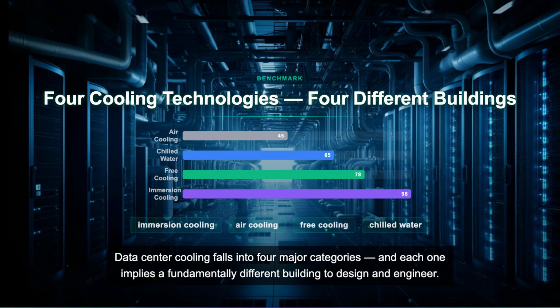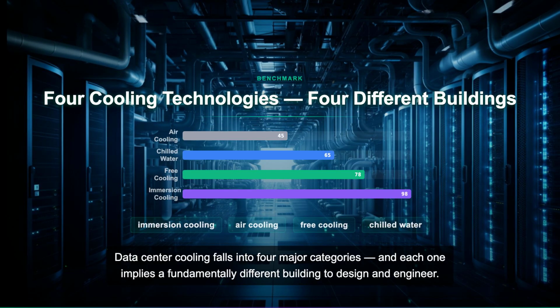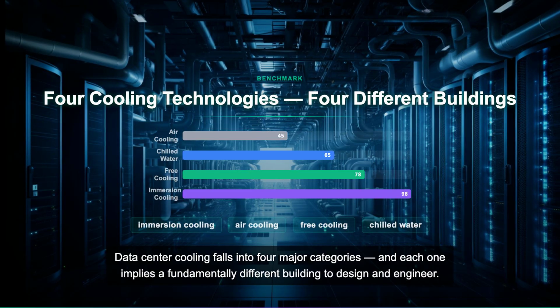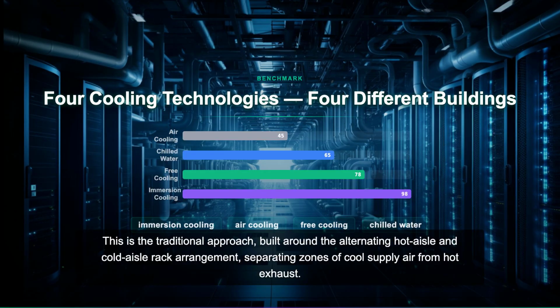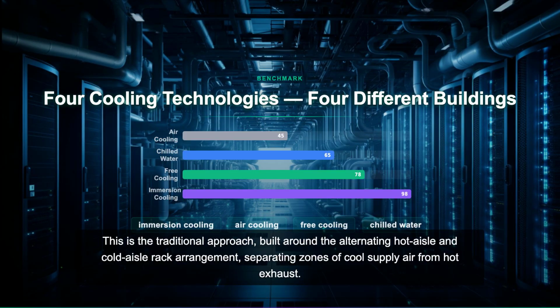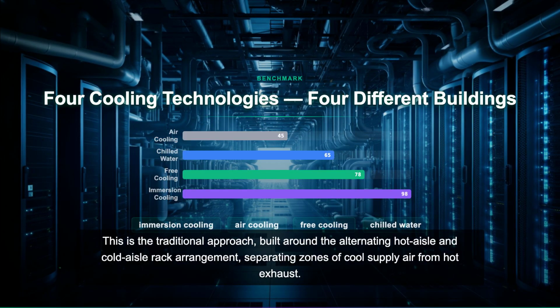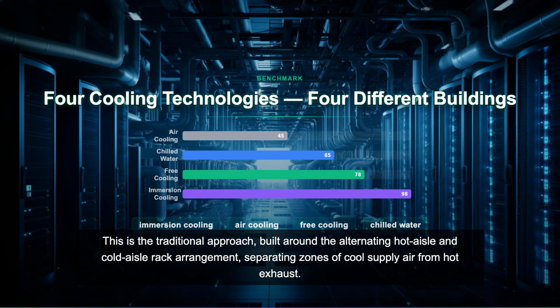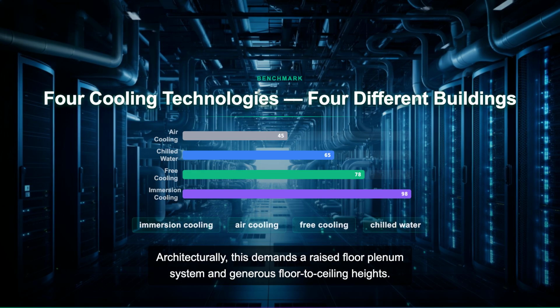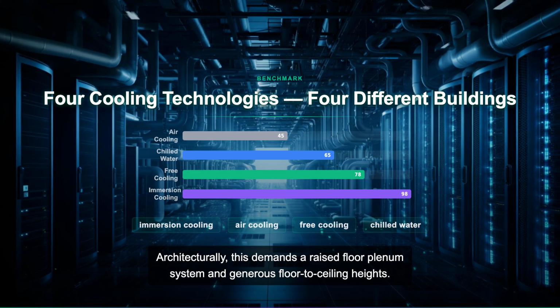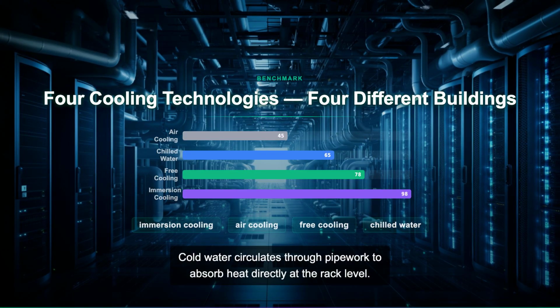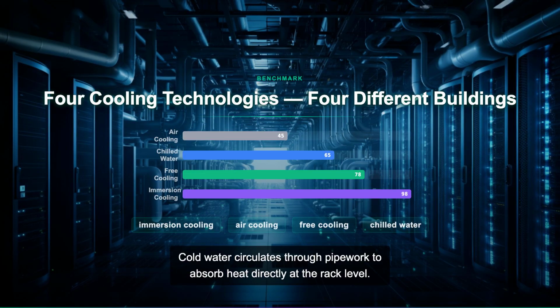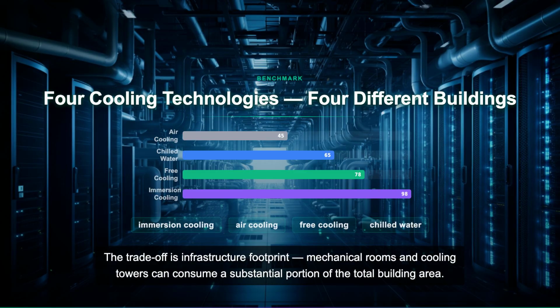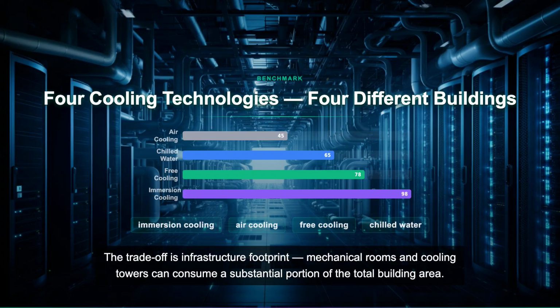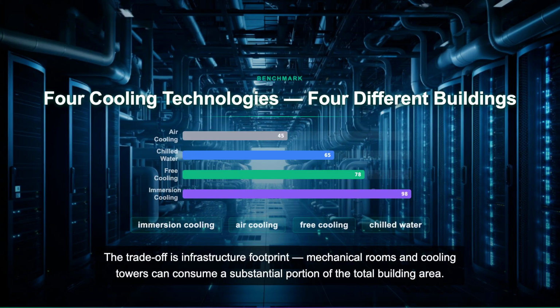Now let's get into the practical core. Data center cooling falls into 4 major categories, and each one implies a fundamentally different building to design and engineer. First, air-based cooling. This is the traditional approach, built around the alternating hot aisle and cold aisle rack arrangement, separating zones of cool supply air from hot exhaust. Architecturally, this demands a raised floor plenum system and generous floor-to-ceiling heights. Second, chilled water cooling. Cold water circulates through pipework to absorb heat directly at the rack level. The trade-off is infrastructure footprint. Mechanical rooms and cooling towers can consume a substantial portion of the total building area.